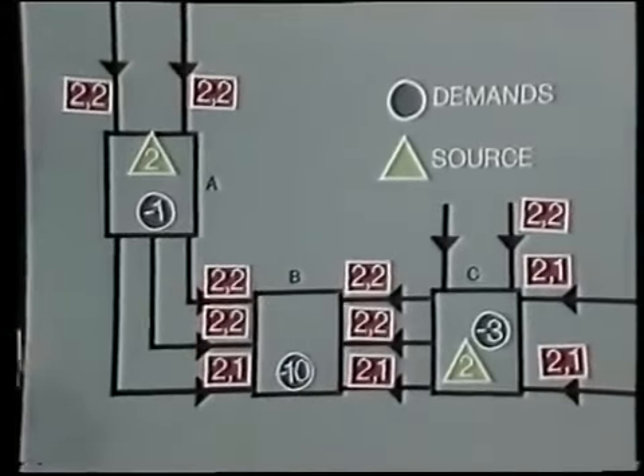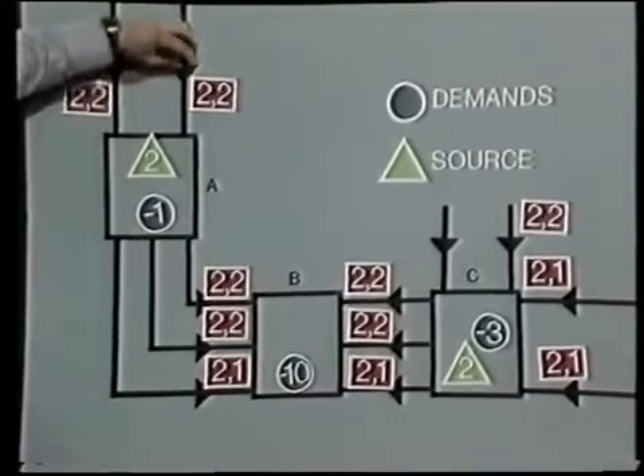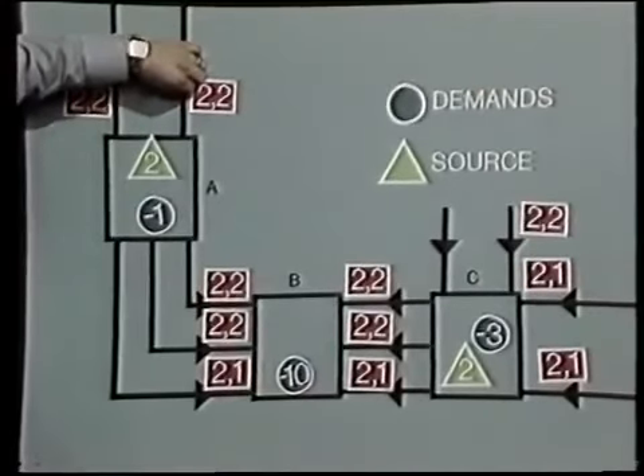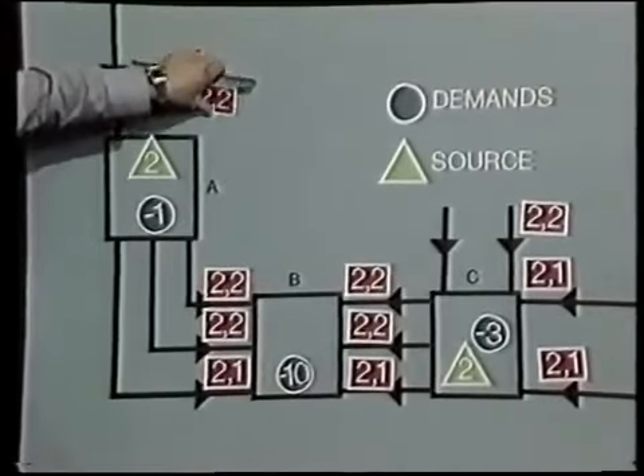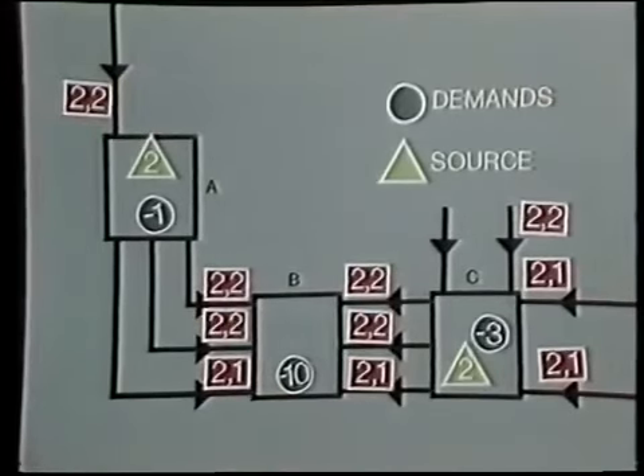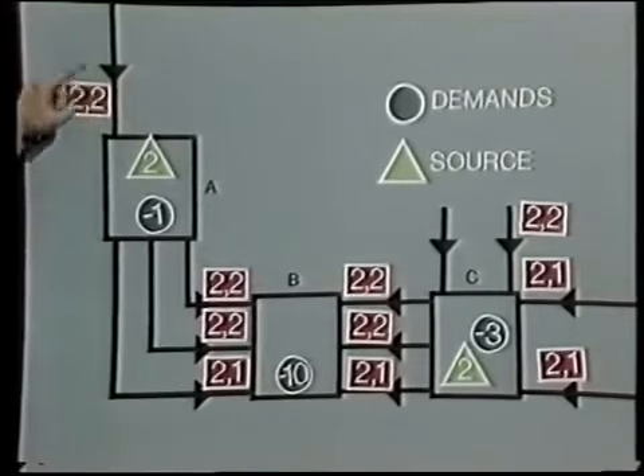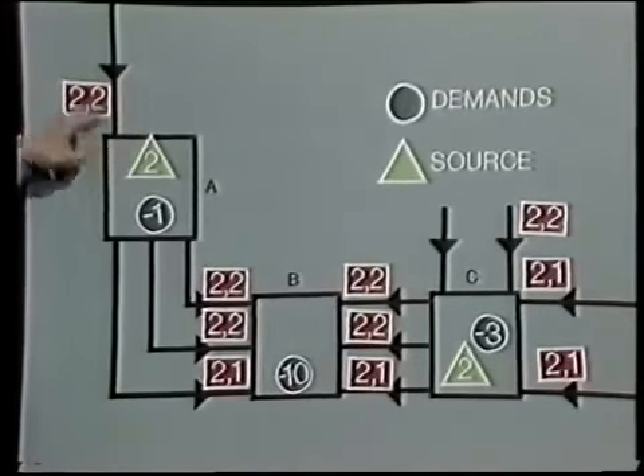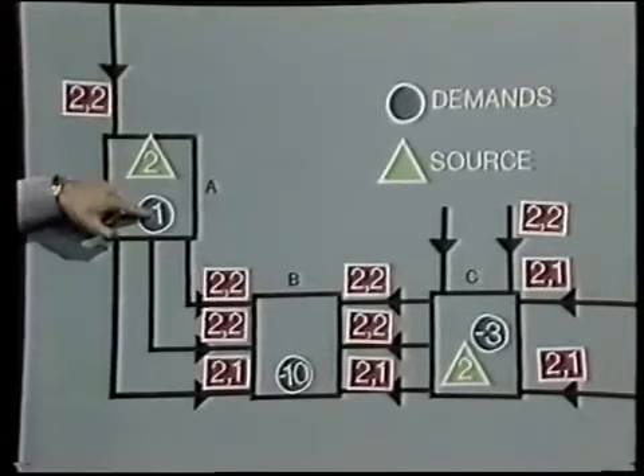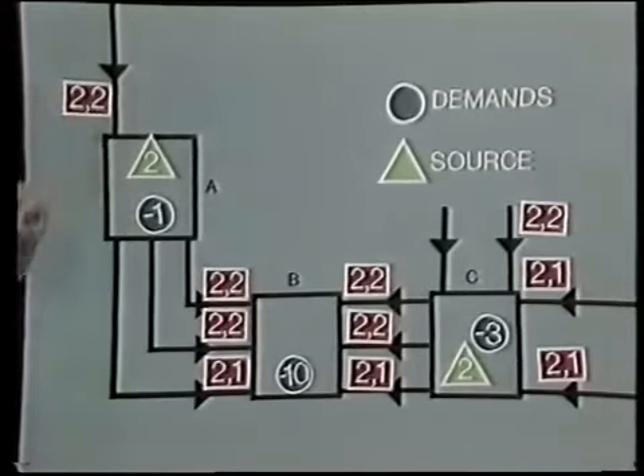However, suppose we look at the line into A, this line — this is a critical line. If this one went down, we are in trouble. We only have 2 gigawatts coming in on this line, plus 2 gigawatts generated locally, making 4, minus 1 for the local demand, which means we only have 3 left to pass on to B.